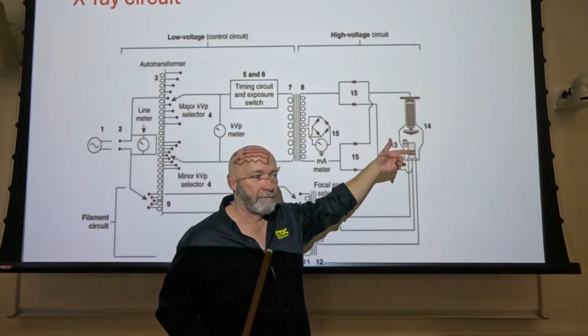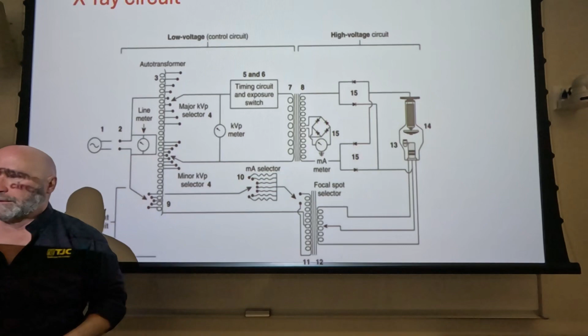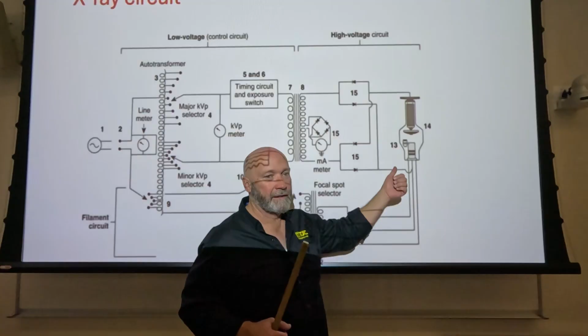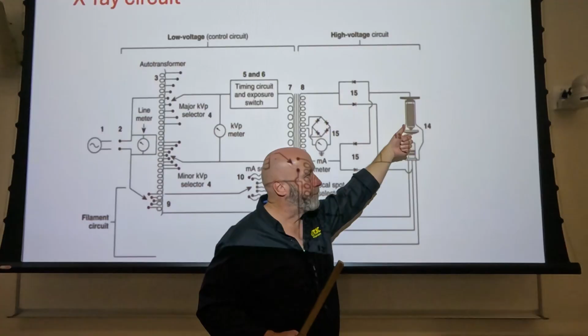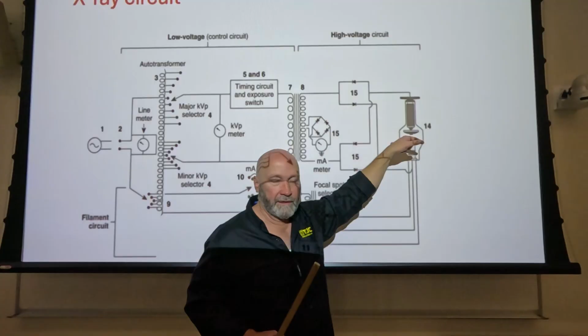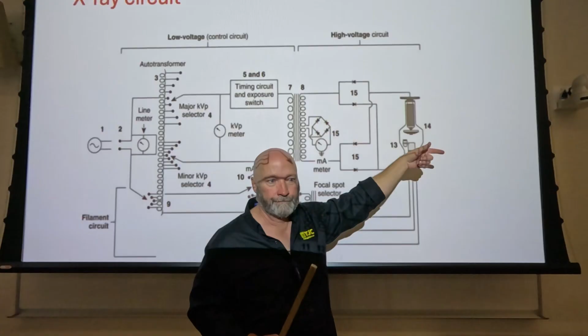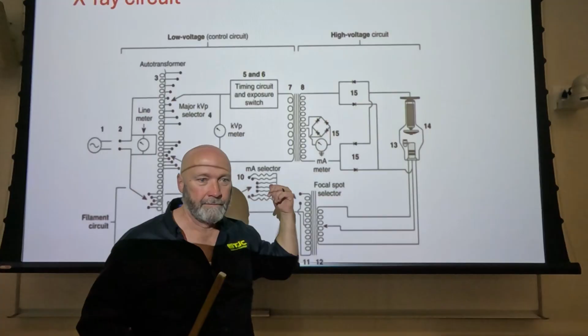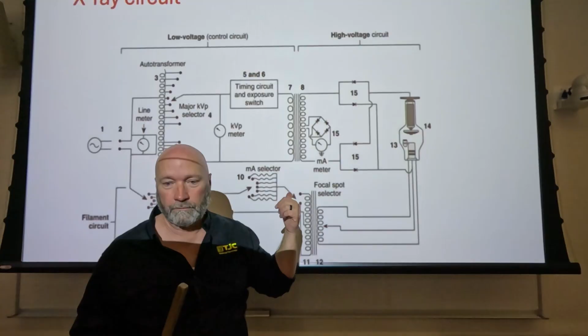The more kinetic energy they have, the more energy they have to lose. The more energy they have to lose, the higher the X-ray beam. Remembering how brems are created, they lose energy, slow down, lose energy. The more energy they have, the more energy they lose, and the X-ray photon that's created is going to be proportional to how much energy they lose. So you can calculate the energy of an X-ray photon based on how much it lost. So incoming energy, if it comes across the tube with 100 kilovolts worth of energy and it loses 99, then that electron still has 1 kilovolt worth of energy, and what we have then is a 99 kVp X-ray photon, right? So how are you going to get a 99 kVp X-ray photon if you only set 50 kVp? You don't. Right. So that's what controls your brems spectrum.